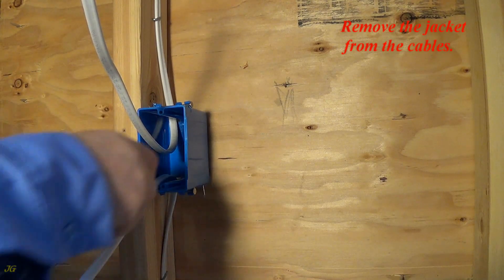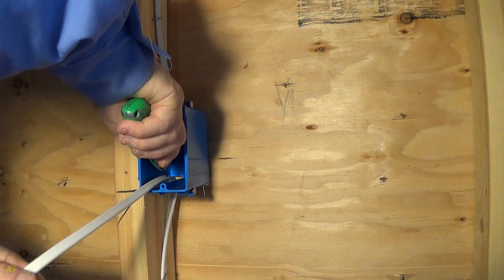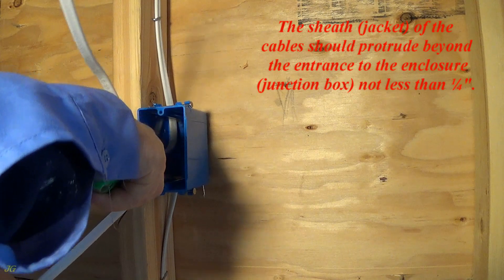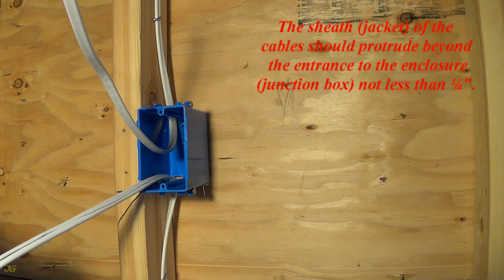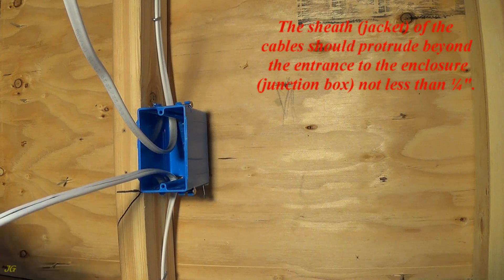Remove the jacket from the cables. The sheath jacket of the cables should protrude beyond the entrance to the enclosure junction box not less than ¼ inch.